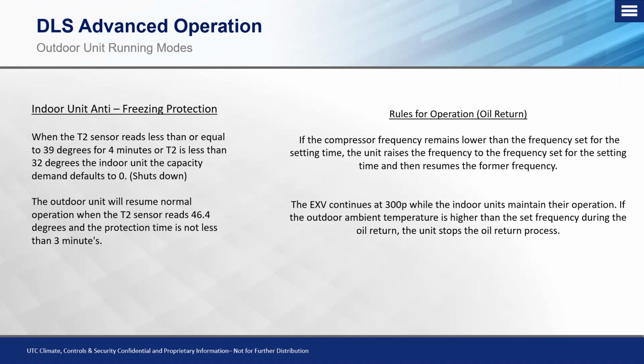Okay, which means when it goes into an oil recovery mode, if they're all in heat, they're going to continue to stay in heat. However, the EXV, if it's at a lower pulse, let's just say, for example, while it was running in normal, it was at 250 pulses, and it goes into an oil recovery mode. The only difference is that now it's going to open up to that 300 pulse. So essentially, we're opening up the valve, and the compressor frequency or the running frequency increases to try to flush that oil back to that compressor.